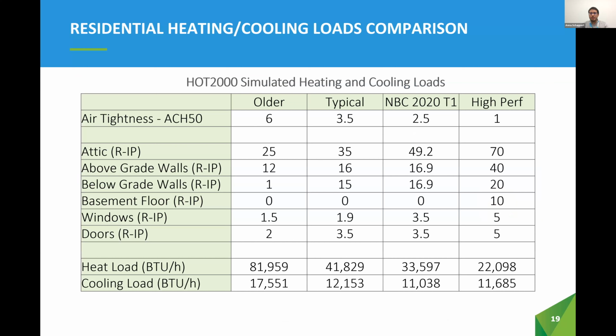As an illustrative example, here we show the HOT2000 modeling of heating and cooling loads for some prototypical dwellings, a 1,500 square foot single detached bungalow in Winnipeg. In each case, we vary the air tightness as well as aspects of the building enclosure to represent several different vintages and associated levels of performance. These range from a relatively leaky and moderately insulated enclosure, typical of an older home, in the leftmost column, to the near net zero high performance home on the right.